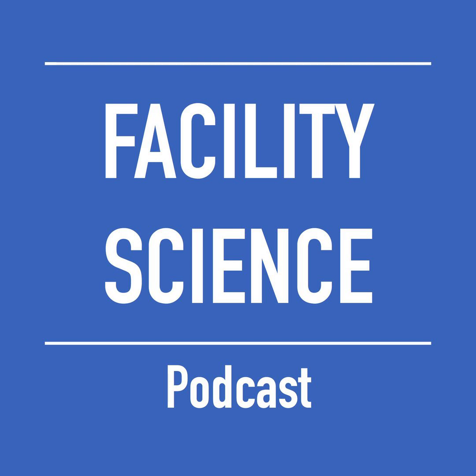So a building like this will have transformers inside the building, in addition to the one outside that the utility services. These transformers step the voltage down to the regular line voltage in order to make that 120 volts available, or the 208 that you might need to service appliances. So in a typical facility, the 480 volt service will enter the building and land on some type of switchboard. Some people might call this the main switchgear. Others reserve the term switchgear for medium voltage and higher, but you'll probably hear both. The switchboard will likely include a disconnecting device, probably a circuit breaker, maybe even a remotely operable circuit breaker that will allow disconnection of utility power.